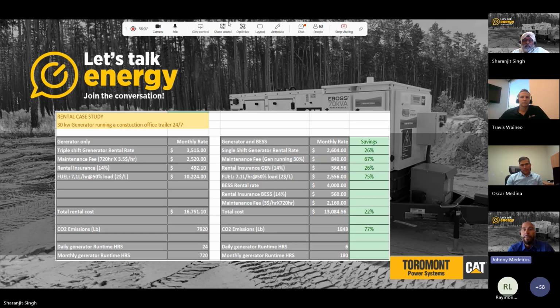And the big impact is fuel consumption. Because the generator only runs 180 hours, and the battery picks up the load the rest of the time, there are economies there. Assuming the customer pays $2 a liter, it'd be about 75% savings.